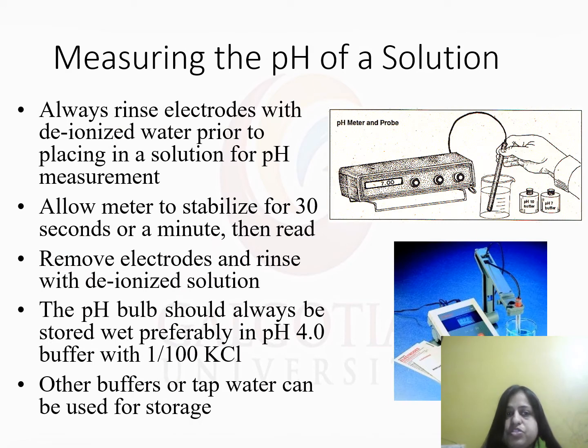When measuring the pH of a solution, always rinse the electrode with deionized water prior to placing it in the solution for pH measurement. Allow the meter to stabilize for 30 seconds or a minute, then read. Remove the electrode and rinse with deionized water. The pH bulb should always be stored wet, preferably in pH 4 buffer with 1 in 100 KCl. Other buffers or tap water can be used for storage.